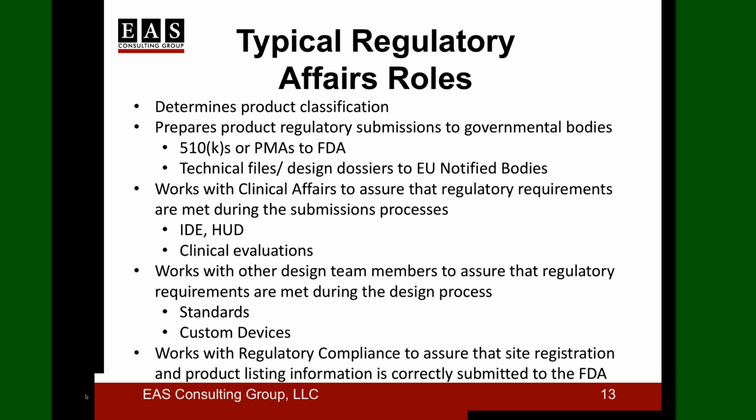So for medical devices, you not only have to be concerned with the quality laws and requirements, such as with FDA, which is 21 CFR 820, which is the QSR; 803, which is the special complaint MDR, medical device reporting; 806, which is corrections and removals; and 821, which is tracking.